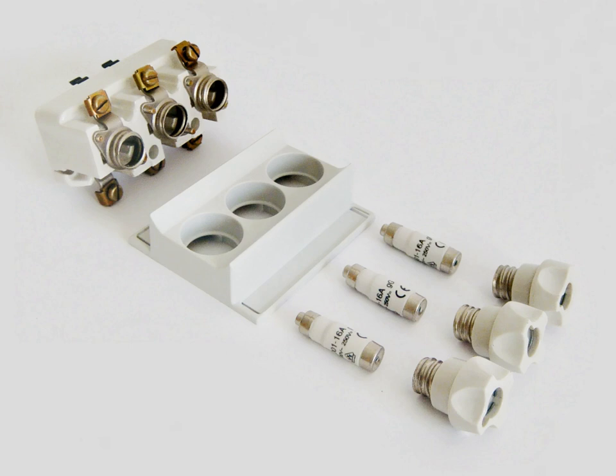The first letter is A if the fuse is for short circuit protection only; an associated device must provide overload protection. The first letter is G if the fuse is intended to operate even with currents as low as those that cause it to blow in 1 hour. These are considered general purpose fuses for protection of wires. The second letter indicates the type of equipment or system to be protected.